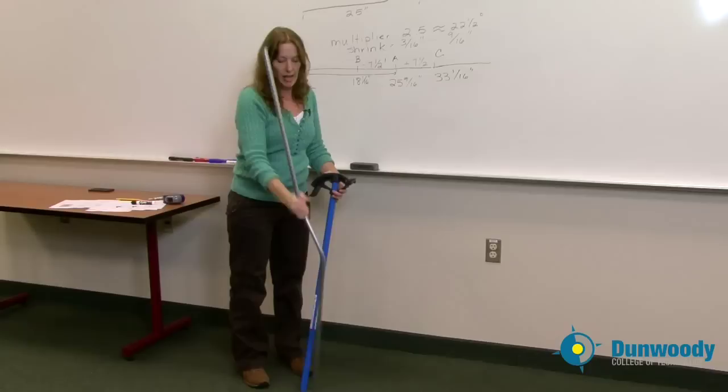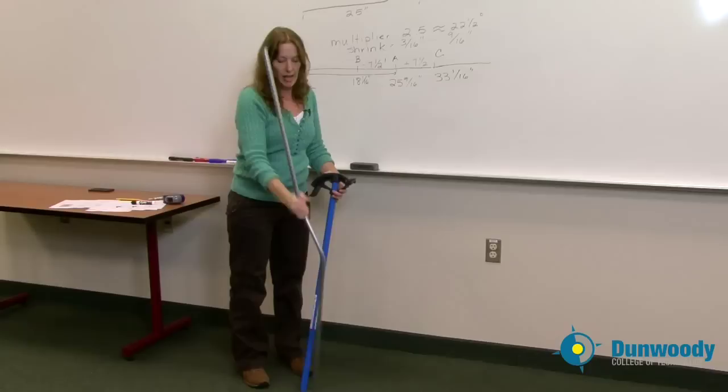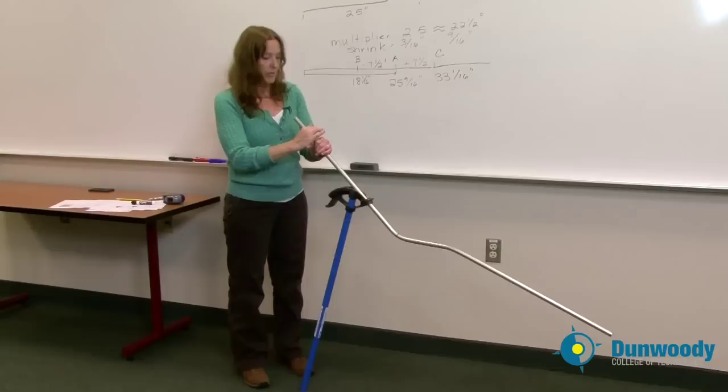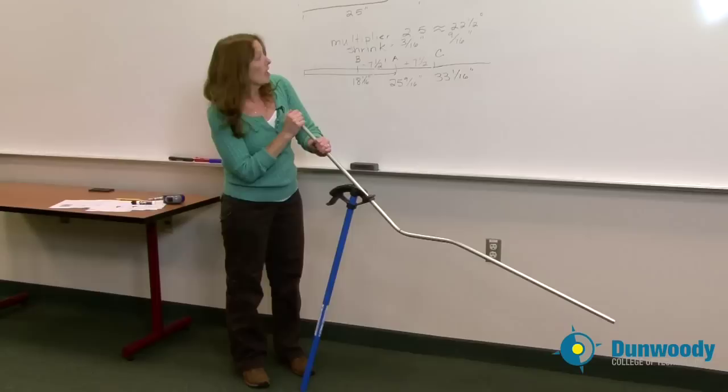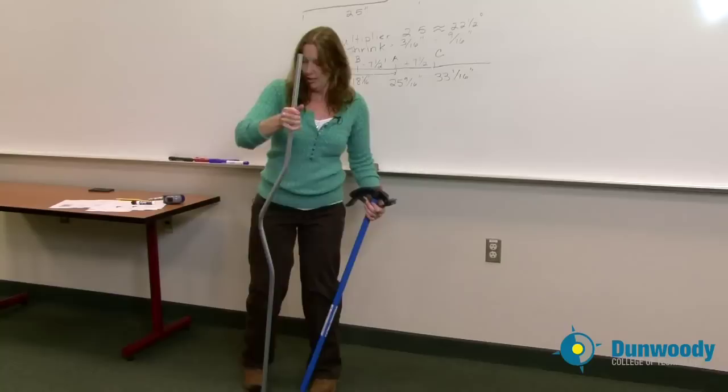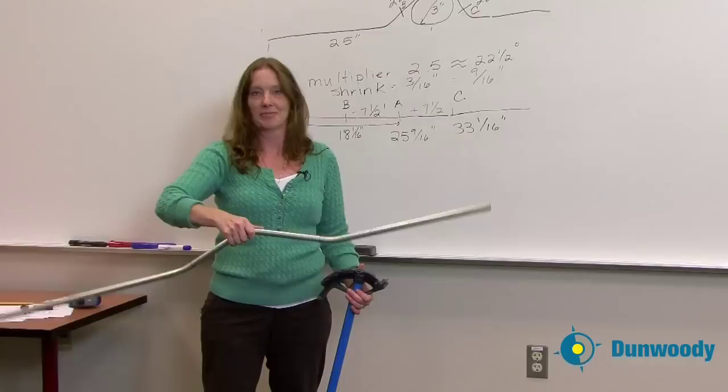I want to pull my pipe completely out of the bender and once again just like on my four-bend saddle I want to bend towards the obstruction. So I'm going to put my conduit in here, match it up to my arrow again because that's my second bend. Make sure my conduit stays nice and straight and I'm going to again bend it to 22 and a half degrees. Take it down and bend it at that 22 and a half degree mark. And there we have a three-bend saddle.